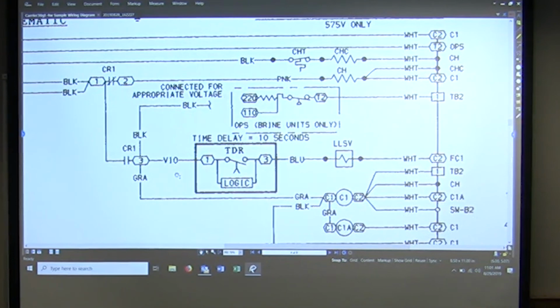So let's say we're not energized. I have power flowing here. What is that doing? Crankcase heater, keeping the liquid refrigerant out of the compressor. Okay, so you have a CH and there's a CHC. What is CHC? That's coming off a different line, but that's tied to a thermostat, right? CR1 goes there and it just energizes that crankcase heater. So if now I energize CR1, what happens? The crankcase heater turns off. This CR1 contact closes, and then I energize all of this stuff.